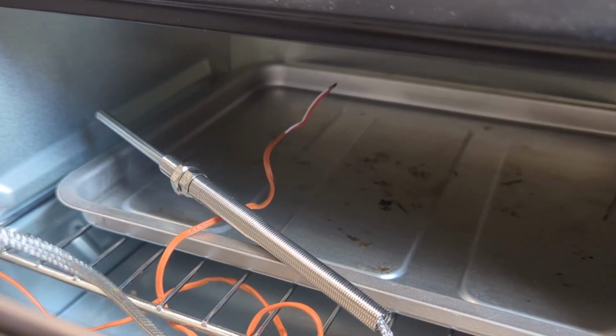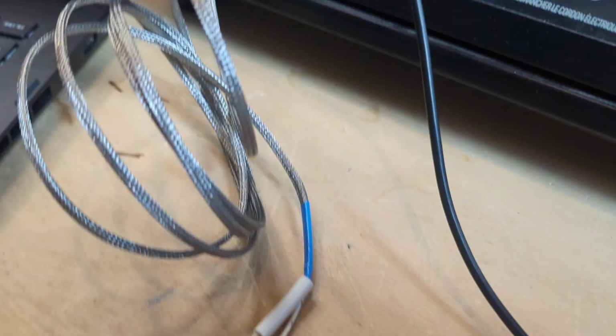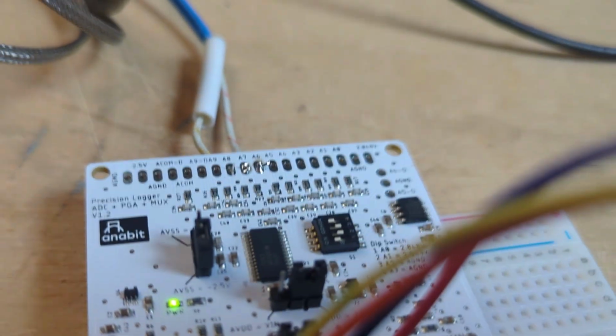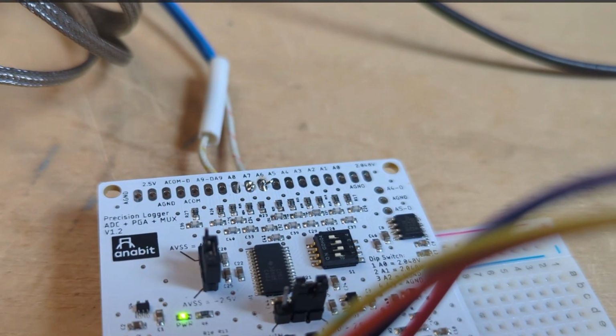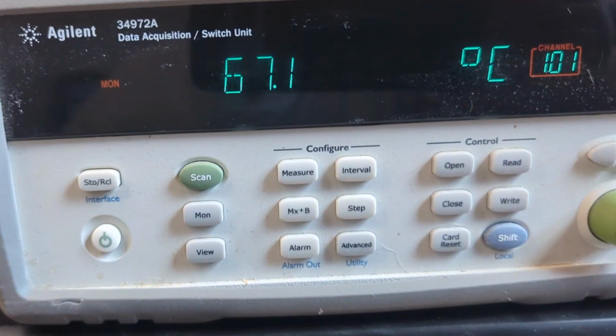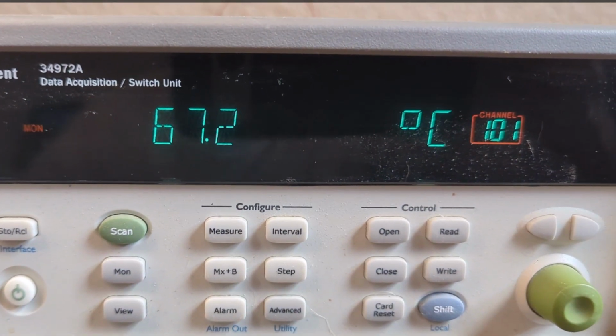So now I'm going to show the oven that is on and is producing some heat. Here is our setup. There is the precision logger. We have a differential channel setup. We have A6 and A7. That's where our thermocouple probe is connected. This wiring goes to our Arduino, the Nano Every that I'm using in this example, using SPI communication. Okay, here is our instrument that's making our reference measurement. This is what the J-type thermocouple is connected to, and we can see we have about 67.2 degrees Celsius.